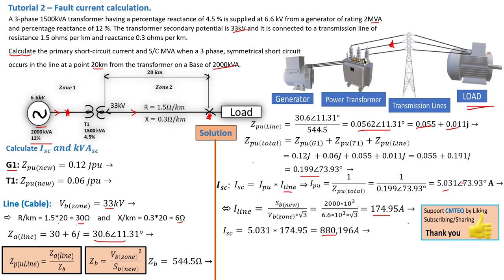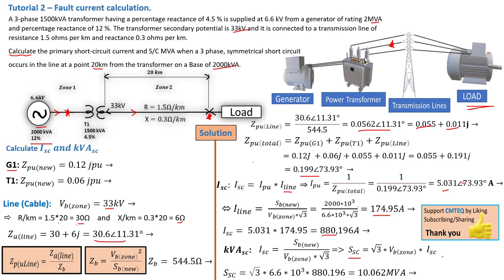Finally, we calculate the short circuit MVA using the same approach — replacing I line with the short circuit current. Short circuit MVA = √3 × 6.6 × 10³ × 880.2, calculated from the primary side of the transformer, giving a short circuit MVA of 10.06 MVA.